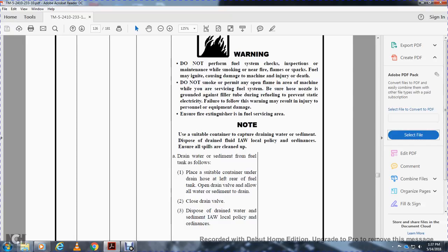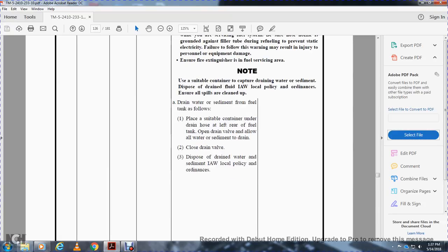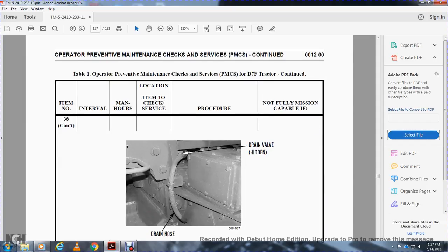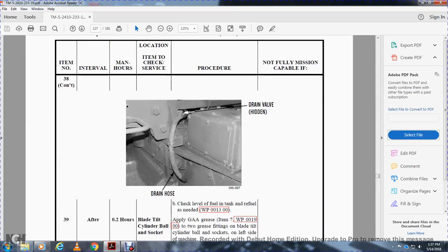Open the drain valve. Allow the water and sediment to drain. Close the drain valve. Dispose of the drain water and sediment in accordance with local policy and ordinances. Item 38, continue: drain valve closed. Check the level of the fuel tank. Refuel as needed. Work package 13.